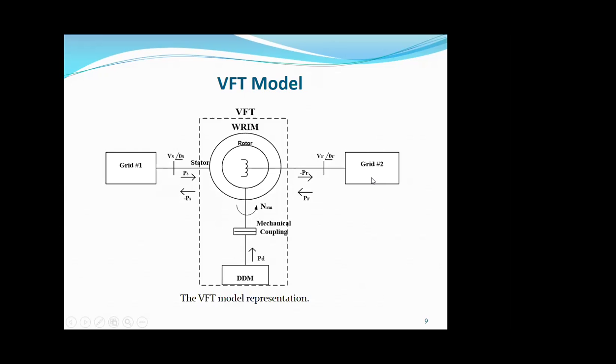As I increase the magnitude of torque applied at the rotor of the wound-rotor induction machine, the magnitude of power flow from grid 1 to grid 2 increases. Similarly, if I want to reverse the direction of power flow, I apply torque at the rotor of the VFT in the clockwise direction, and the power flow direction reverses — earlier it was grid 1 to grid 2, now it becomes grid 2 to grid 1. As I increase the magnitude of torque in the reverse direction, the magnitude of power flow from grid 2 to grid 1 increases.